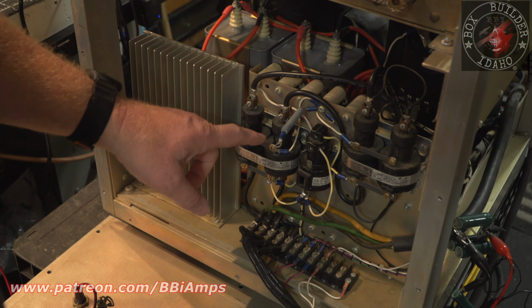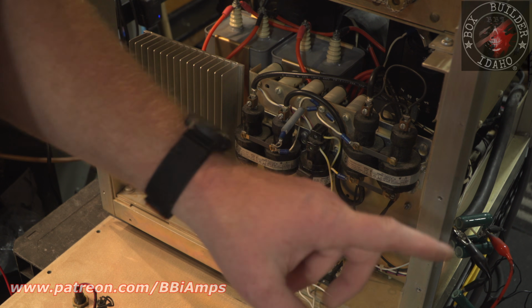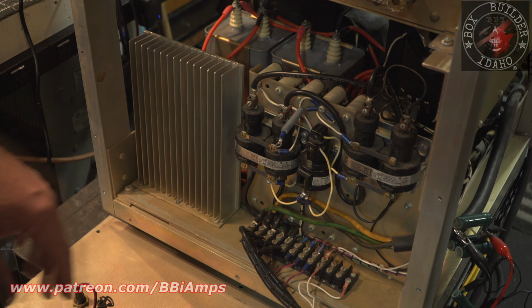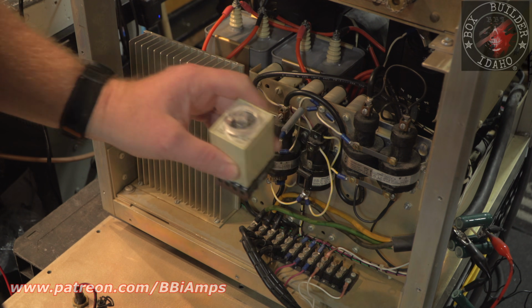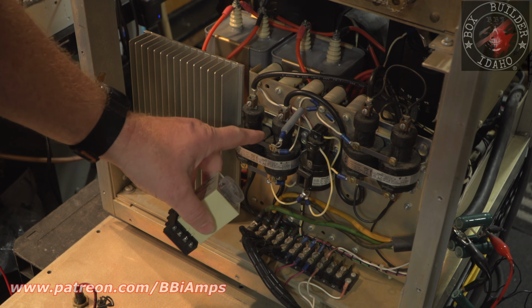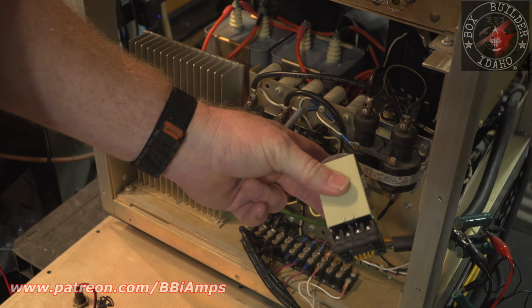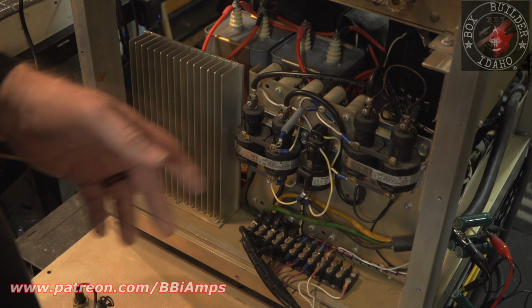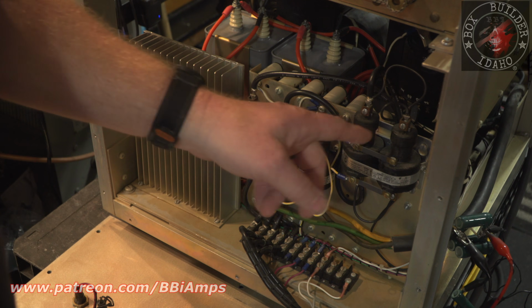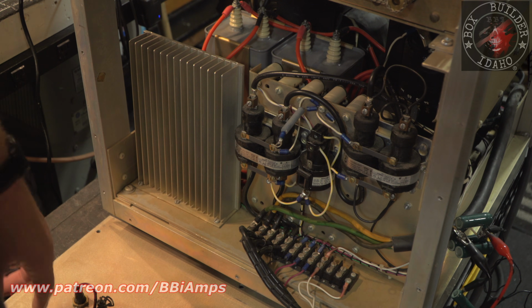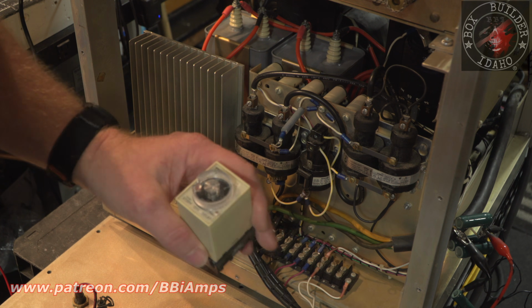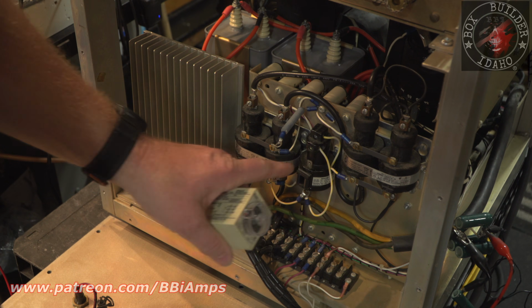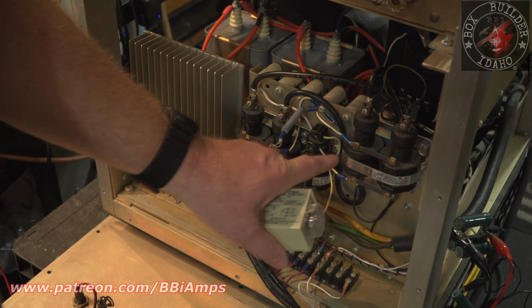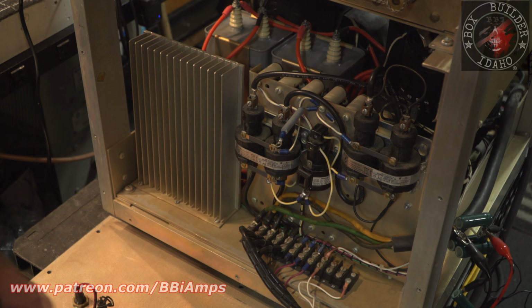When this first contactor closes, I stick with the same 25 ohm resistor. When this first set of contactors closes, it trips this timer, and then I have another two resistors in line, one to power this and one to power that. This will trip this contactor 3 or 4 seconds later, and that in turn drives this contactor.